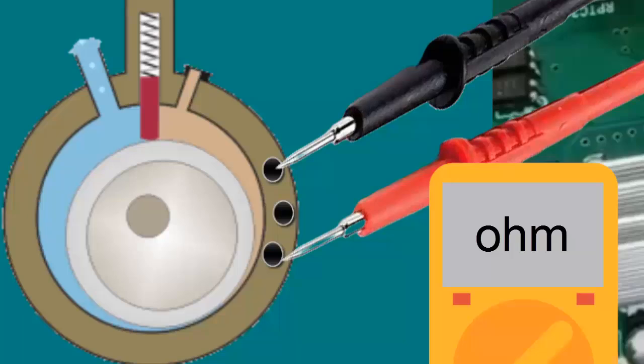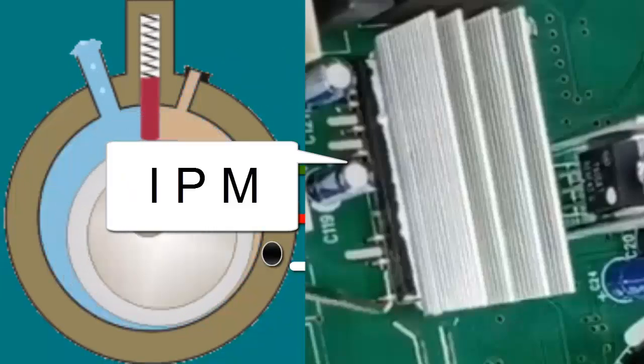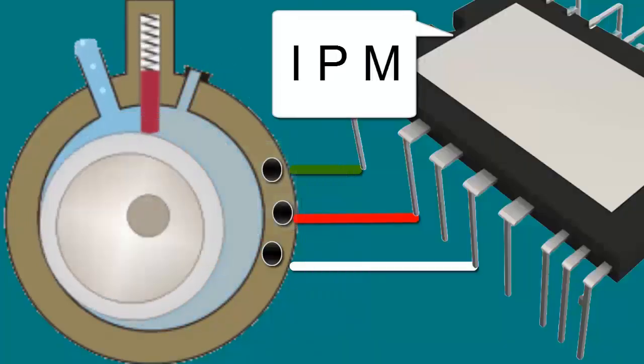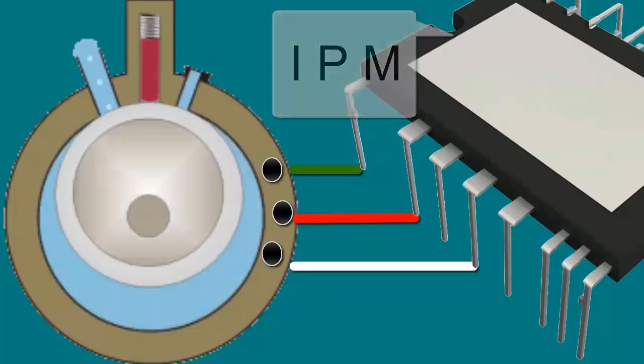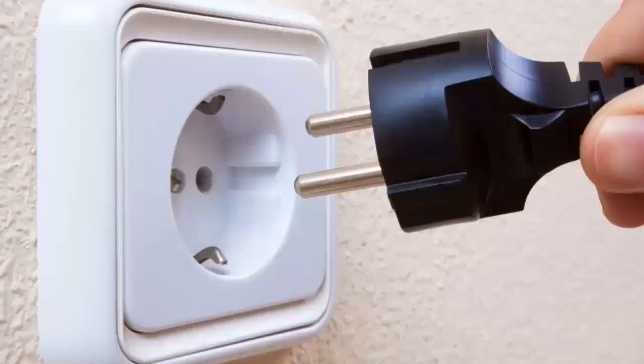E. If no faults are identified in the previous steps and the amperage remains consistently higher than the manufacturer's specifications, there may be issues with the IPM module integrated circuit that supplies current to the compressor. F. When there are problems with the IPM module, an error code often appears to guide the detection of this fault.